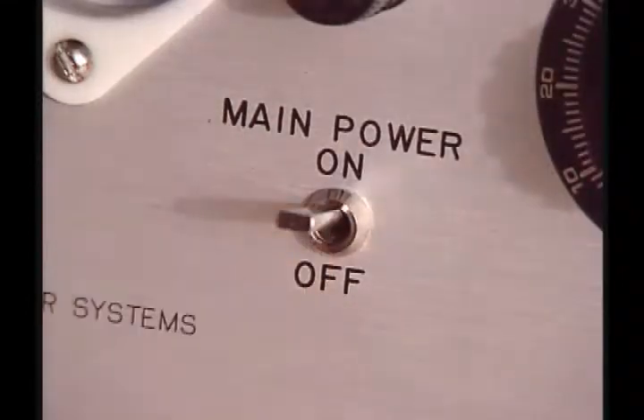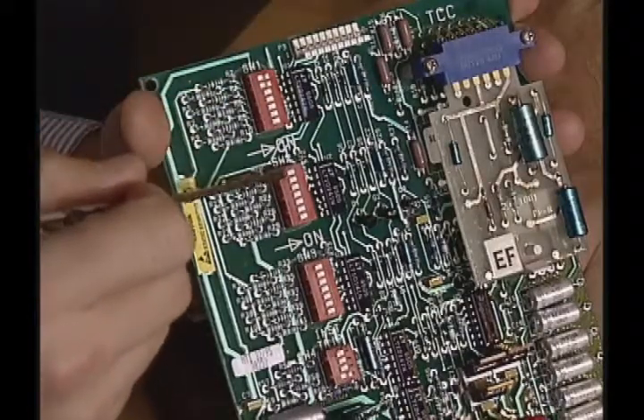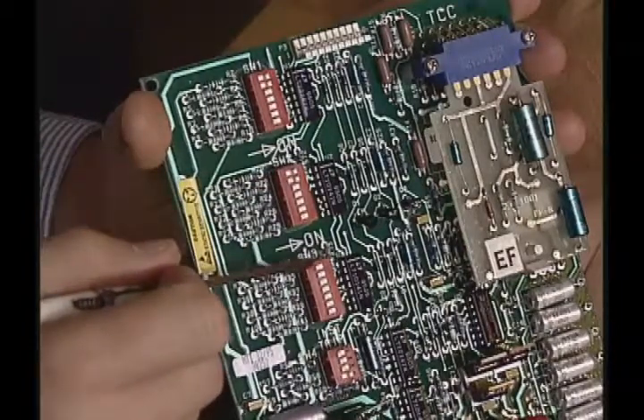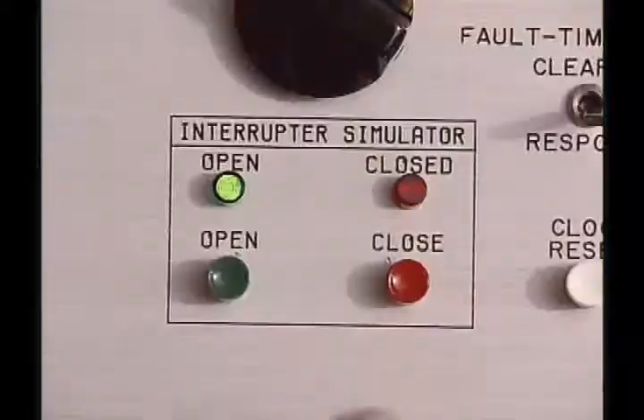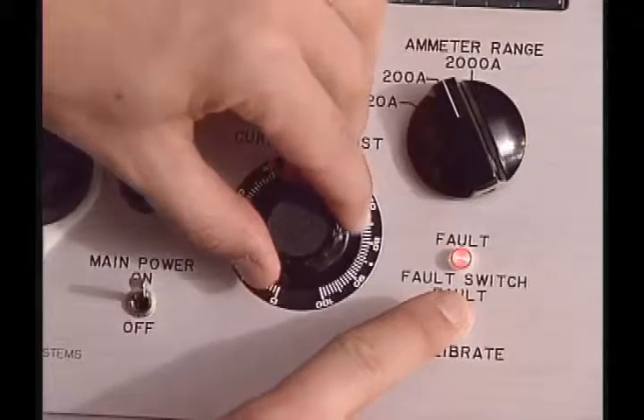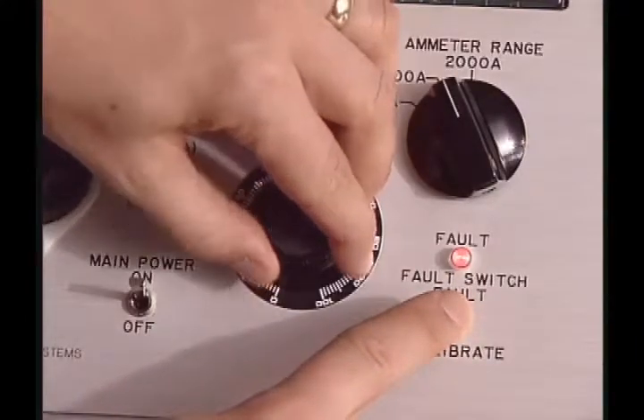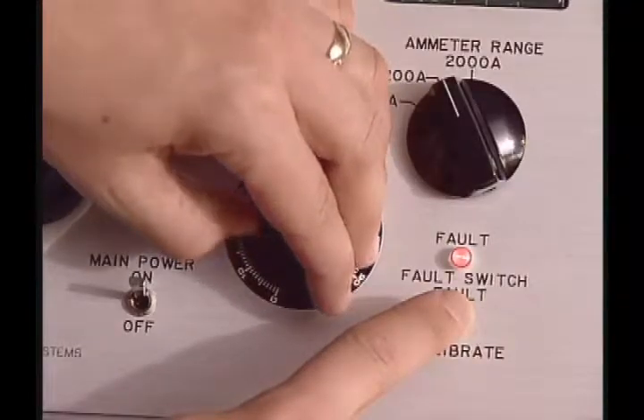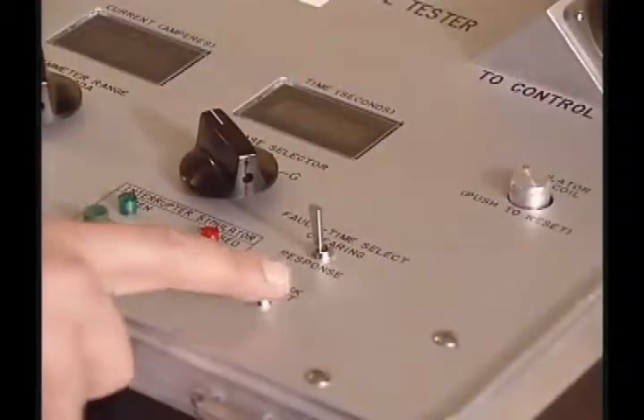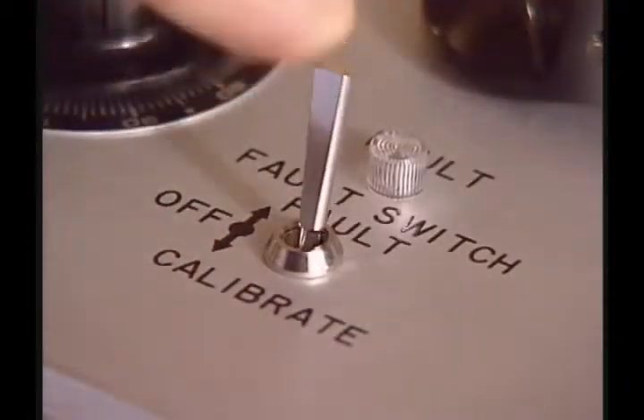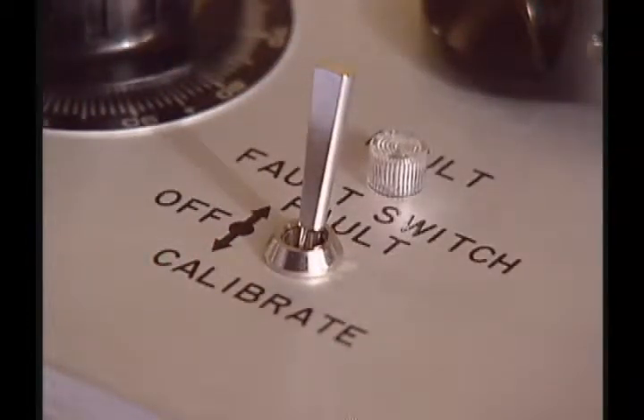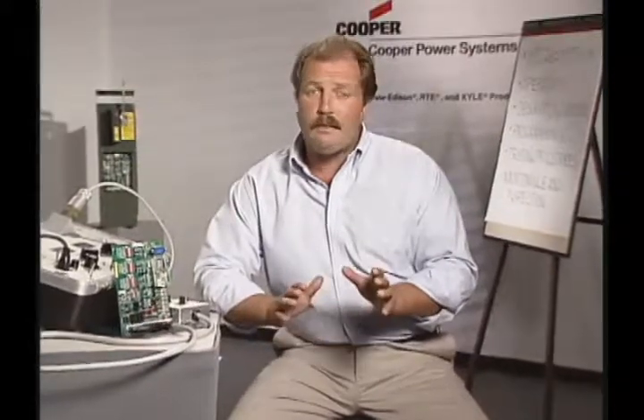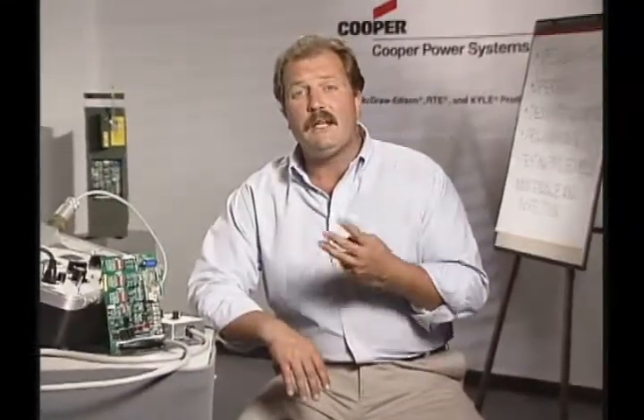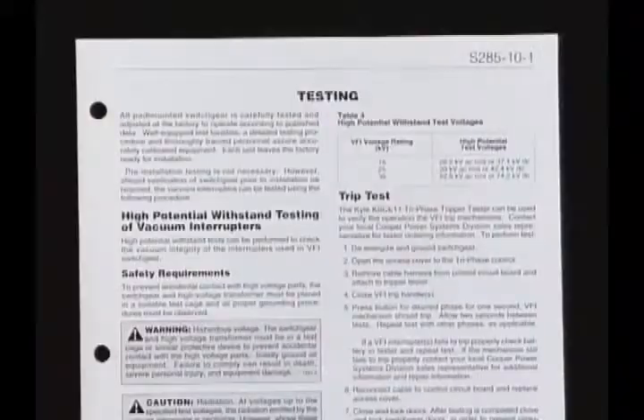Now turn the main power switch on. To perform the time delay trip test, set the minimum trip for each phase to 50 amps. Then set the interrupter simulator to the closed position. Next, hold the fault switch in the calibrate position while setting the desired test current level to 2 times minimum trip for a total of 100 amps. Reset the clock and move the fault switch to the fault position. The time delay reading must be within plus or minus 20% of the published time current curve. To verify proper time delay function, repeat this procedure using at least 3 multiples of minimum trip on each phase.